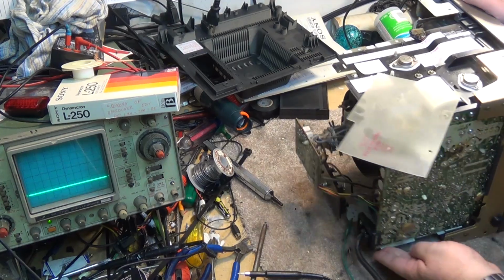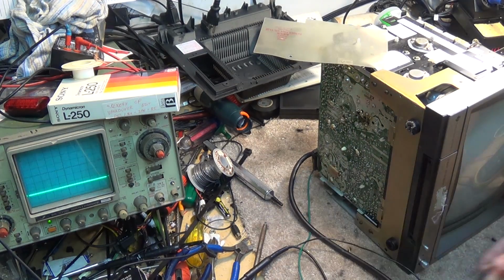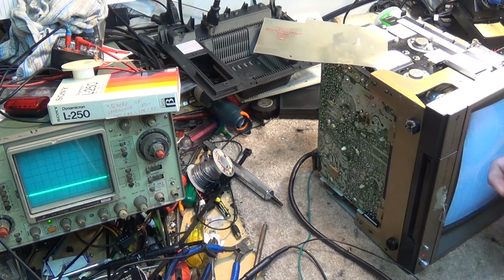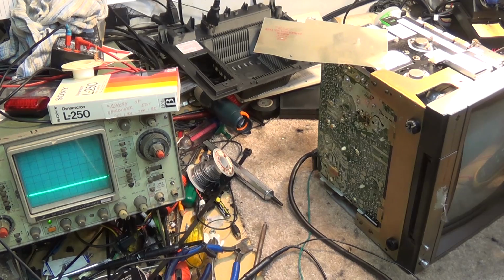We'll turn it around here so you'll see the screen light up. You see? Actually, that's not good, it's too bright. If I bring the voltage up, it's probably going to go into shutdown mode here. There, it's going into shutdown, and it's shutting down when I get my input voltage up to about 85 volts.